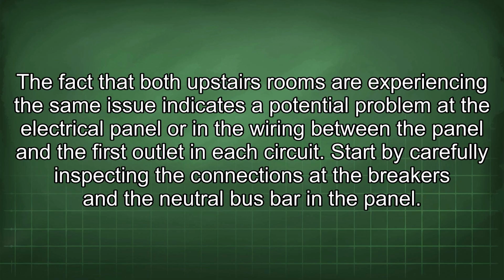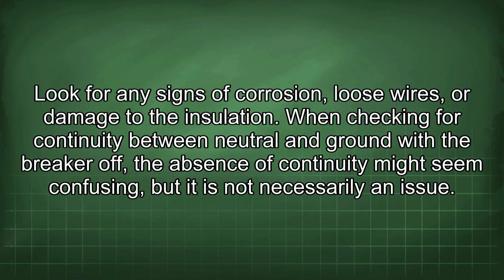The fact that both upstairs rooms are experiencing the same issue indicates a potential problem at the electrical panel or in the wiring between the panel and the first outlet in each circuit. Start by carefully inspecting the connections at the breakers and the neutral bus bar in the panel. Look for any signs of corrosion, loose wires, or damage to the insulation.